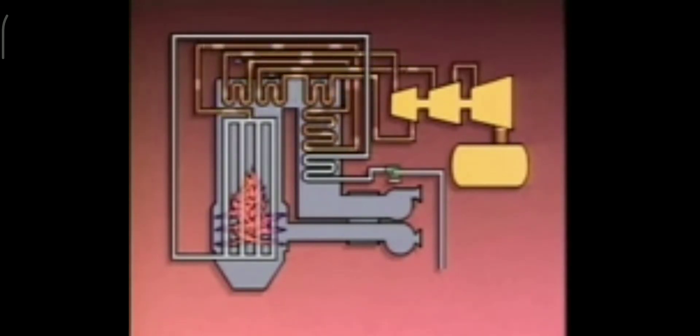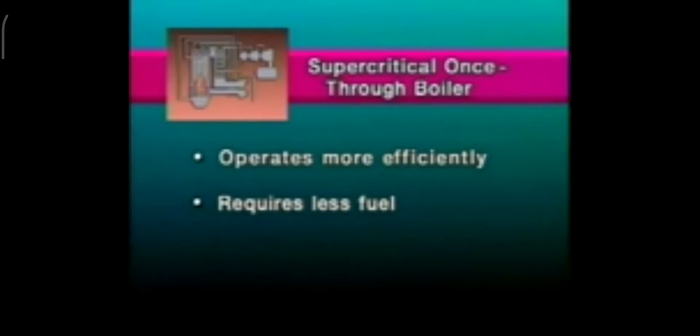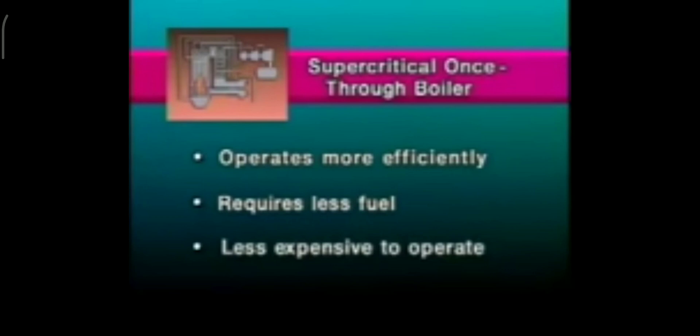The components in the steam flow path are generally the same for supercritical boilers and subcritical boilers. The main advantage of a supercritical once-through boiler is that it operates more efficiently than a subcritical boiler that has to recirculate water in the process of producing steam. A supercritical once-through boiler requires less fuel than a drum-type boiler of the same size to produce the same amount of steam, making it less expensive to operate.